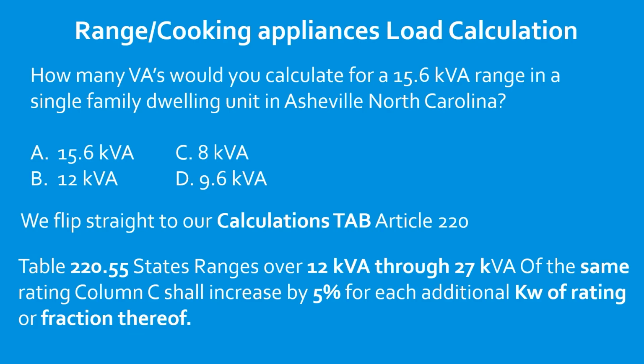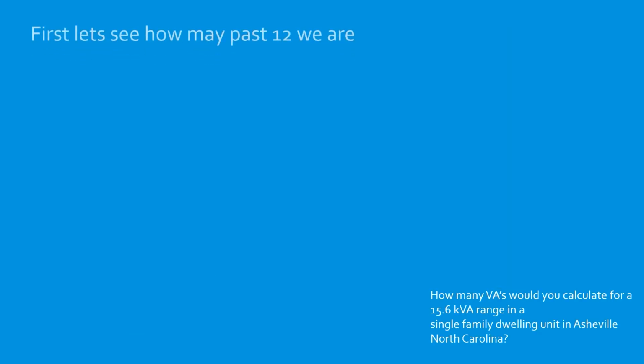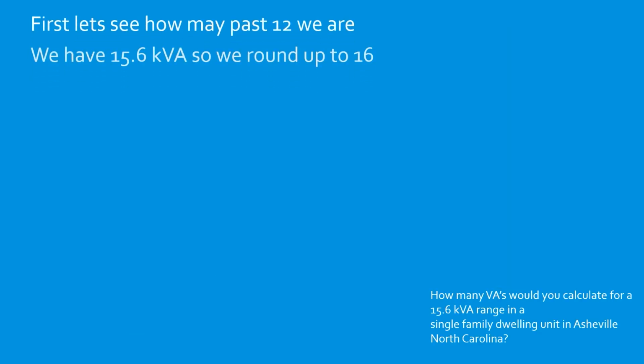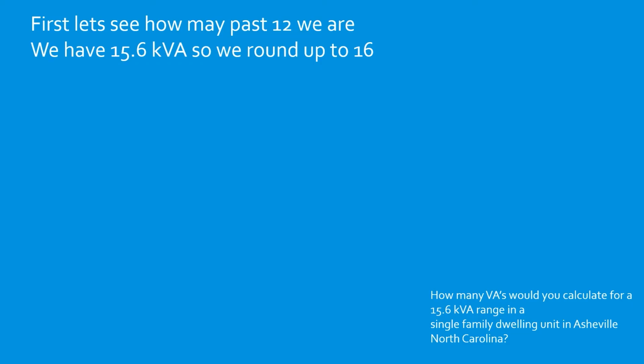12 or fraction thereof. First thing we're going to see is how many we are past 12. We have 15.6, so we're going to round up to 16. We take 16 minus 12, and that's going to give us 4. We are 4 past 12. So now we're going to take our 4, multiply it by 0.05, and that's going to give us 20%.